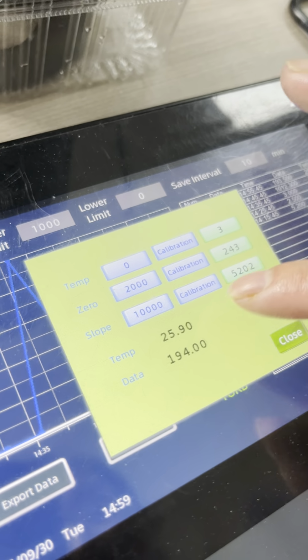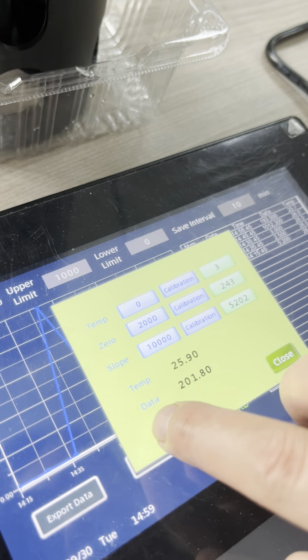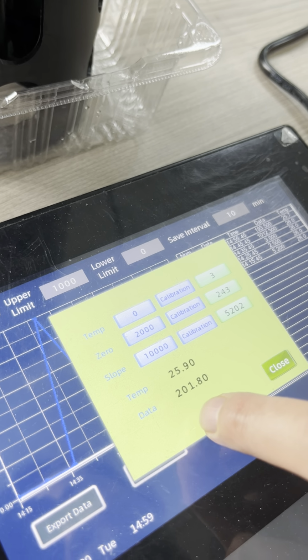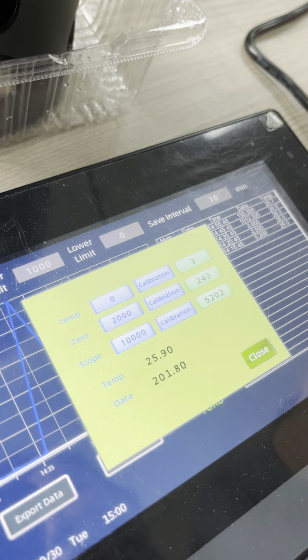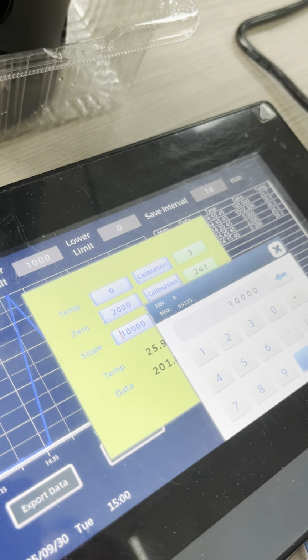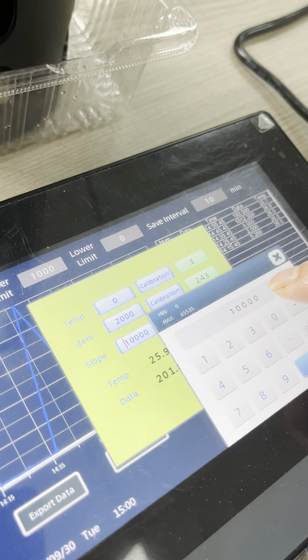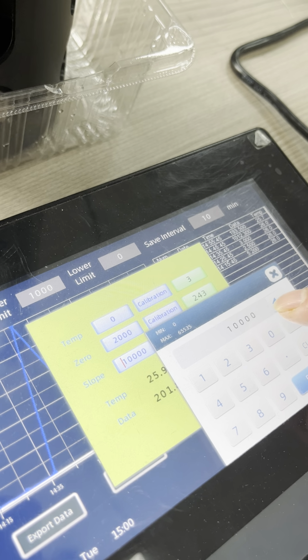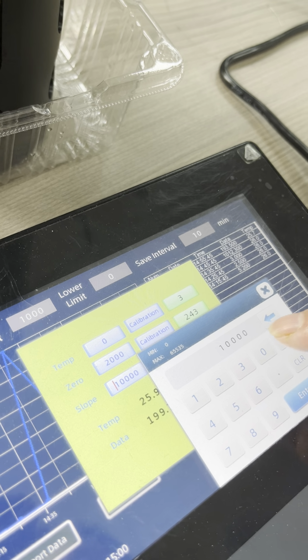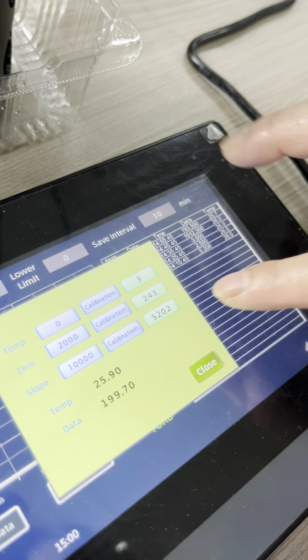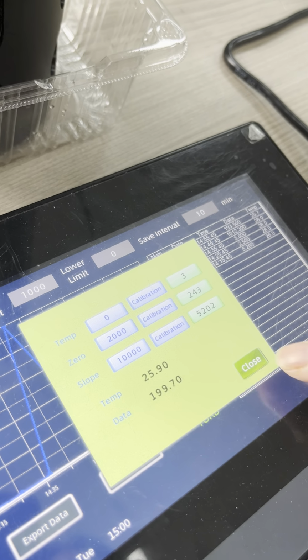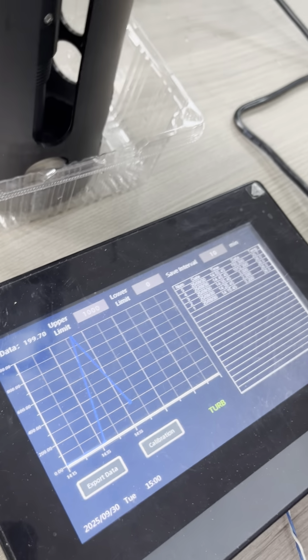Then after 3 minutes, the data here will show the value. After the value is stable, you click here. You input 1000 times 10, that is 10,000. Then click enter, then click calibration. The calibration of turbidity is done.